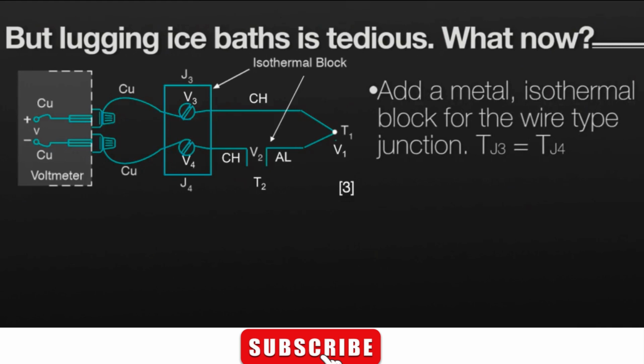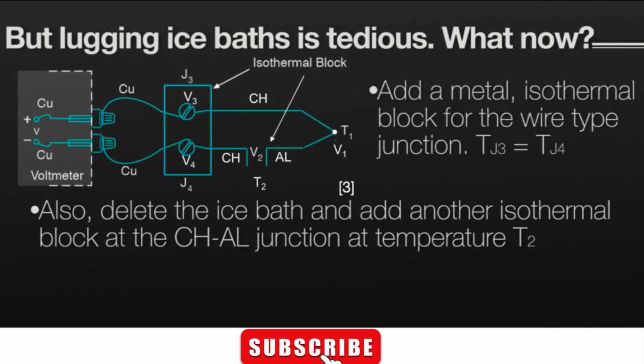Let's insert an isothermal metal block into the system. Isothermal meaning constant temperature. This block creates a junction of dissimilar metals, junction J3, where the copper wire meets the chromel wire, and I abbreviate chromel with a CH. Let's substitute an isothermal metal block at junction J2 for the ice bath that we had before. In addition, we'll string some chromel wire in between these two isothermal blocks. This gives us two more junctions of dissimilar metals, junction J4, where copper wire meets chromel wire, and junction J2, where chromel wire meets alumel wire, abbreviated with the letters AL.